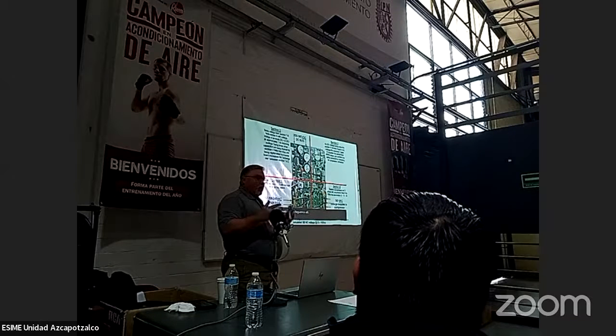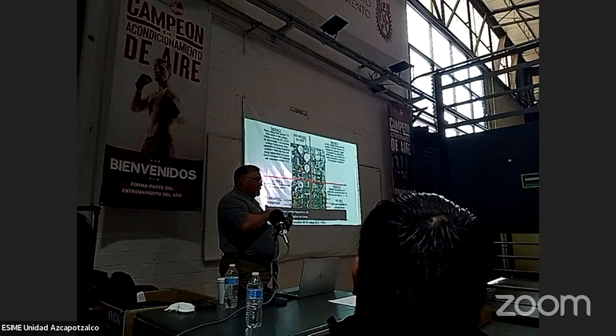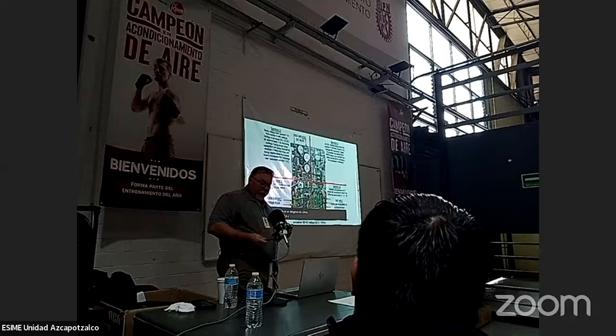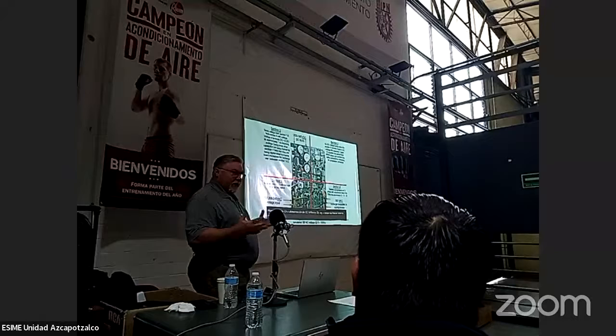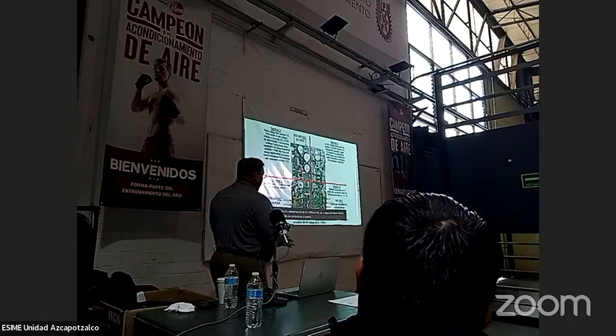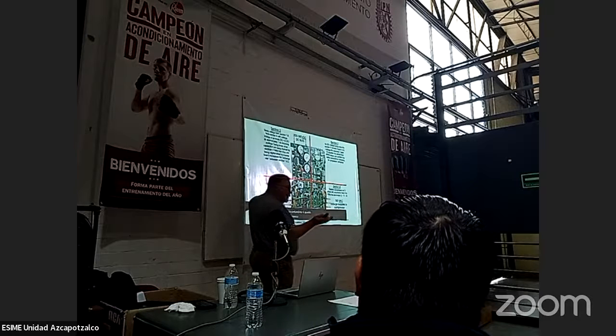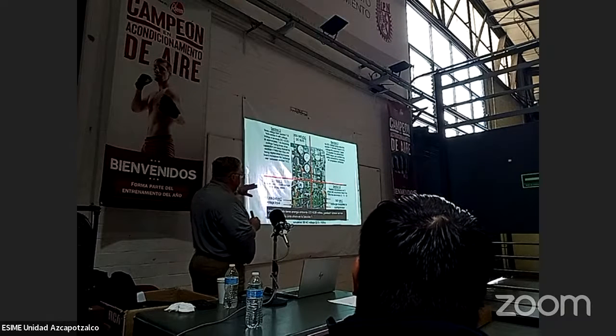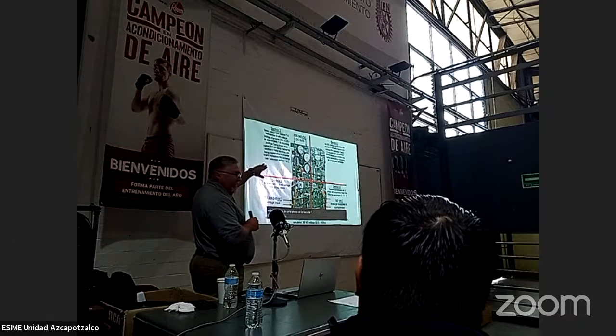Now this is a breakdown of how we convert AC power to three-phase DC power. I'm going to try to make this as technical as possible without confusion, if I can. So when you have incoming power, 220, 208, 230 volts, that voltage is brought into the board. Now in section 1, what we do is supply the voltage to fill up the capacitors. But how do we do that? We first have to convert that to DC power.